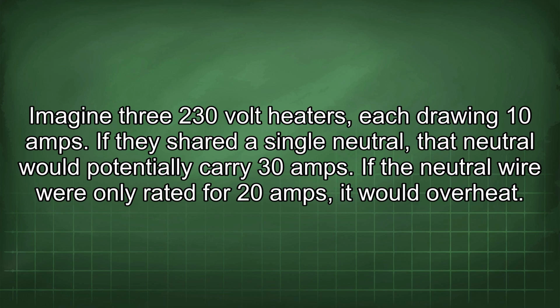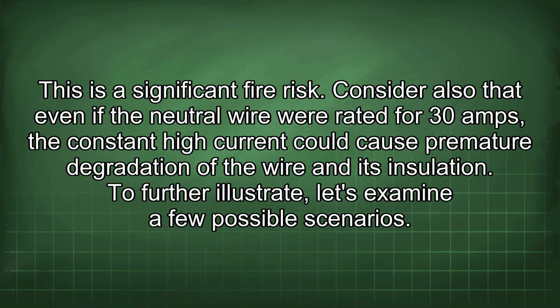Consider the practical implications of sharing a neutral. Imagine 3 230-volt heaters, each drawing 10 amps. If they shared a single neutral, that neutral would potentially carry 30 amps. If the neutral wire were only rated for 20 amps, it would overheat. This is a significant fire risk. Consider also that even if the neutral wire were rated for 30 amps, the constant high current could cause premature degradation of the wire and its insulation.